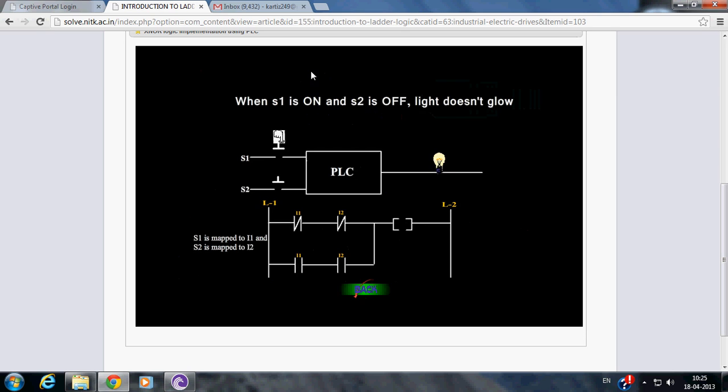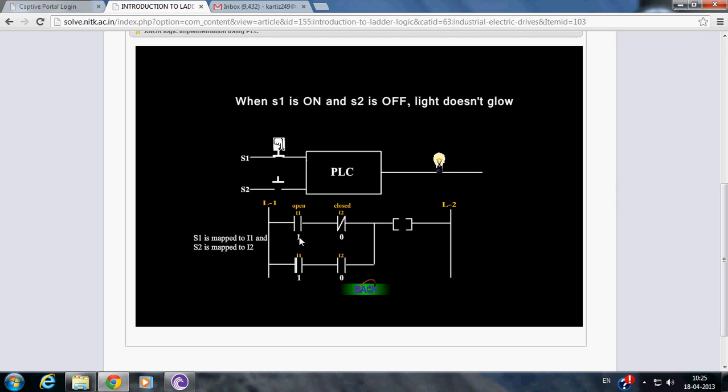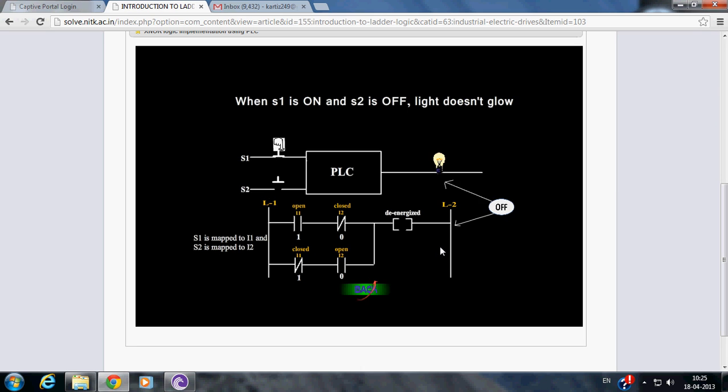Since S1 is mapped to I1 and S2 is mapped to I2, normally close instruction I1 becomes false, normally close instruction I2 becomes true, normally open instruction I1 becomes true, normally open instruction I2 becomes false. Since there is no logical continuity in the rung, the output bulb gets deenergized.